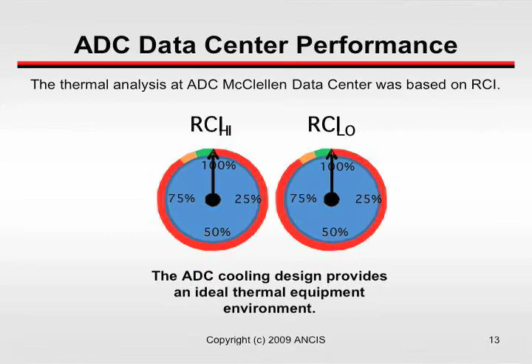So here we have the results of RCI high and RCI low for that previous slide. We did a number of simulations of this data center, which evolved over several months. Remember, RCI high indicates how well you're controlling the upper limit of the recommended range, and RCI low indicates how well you're controlling the lower range.